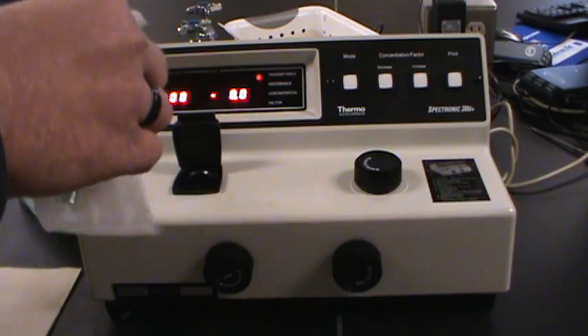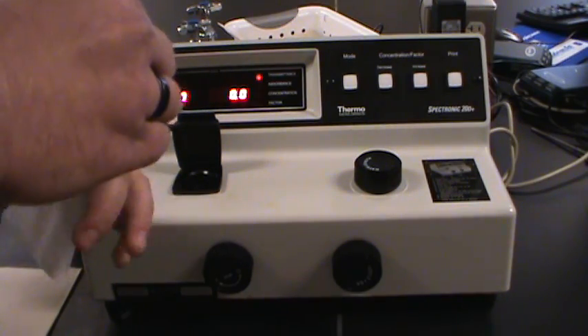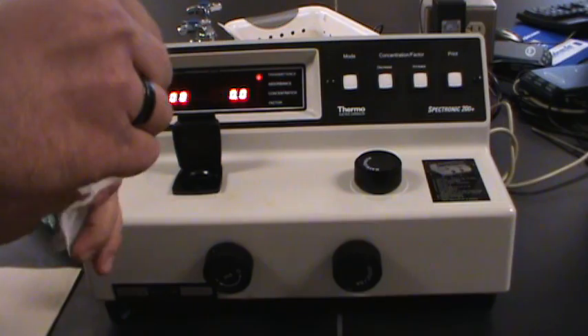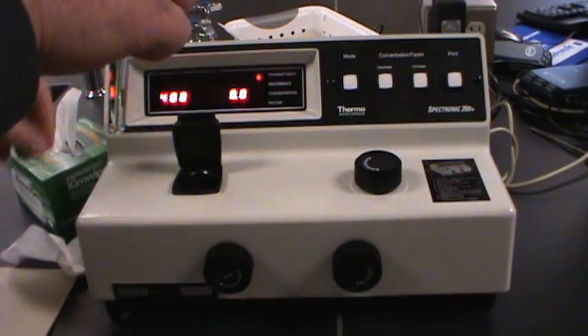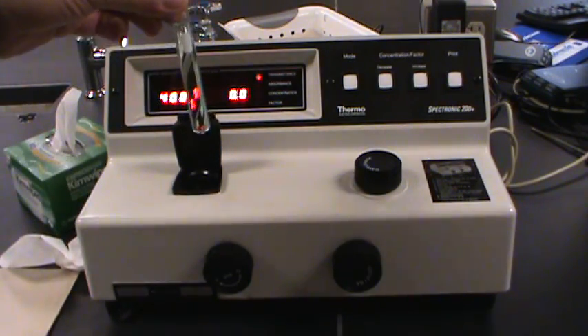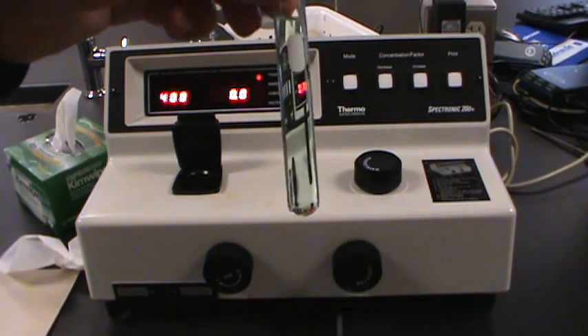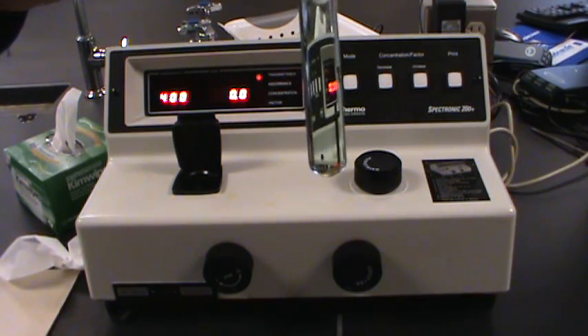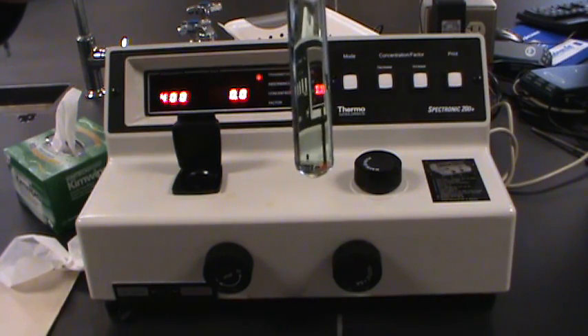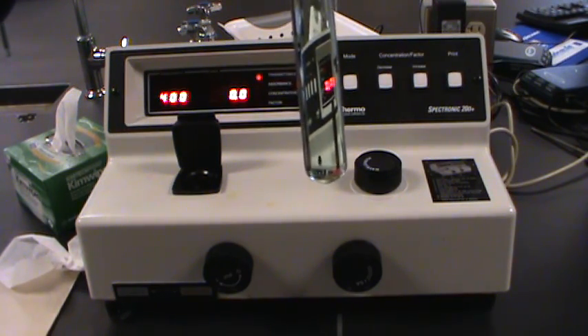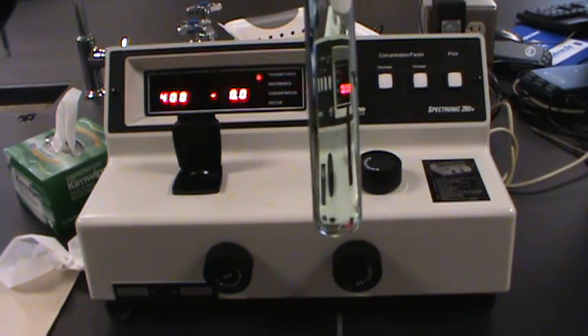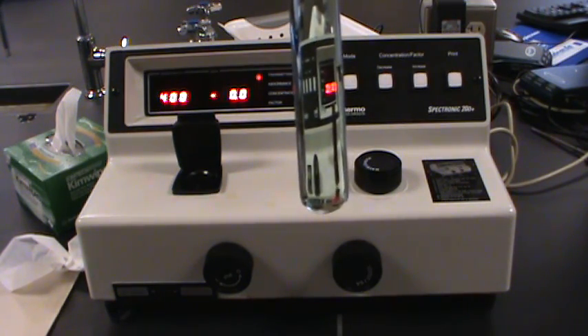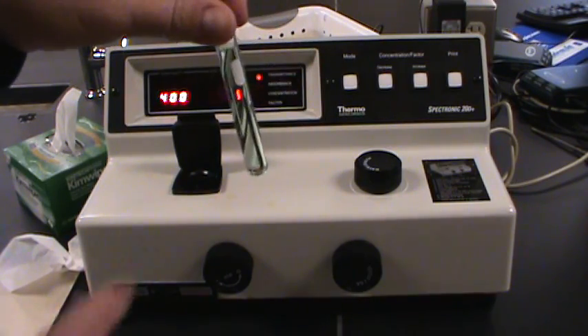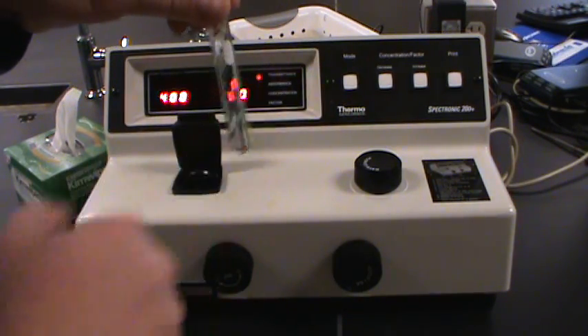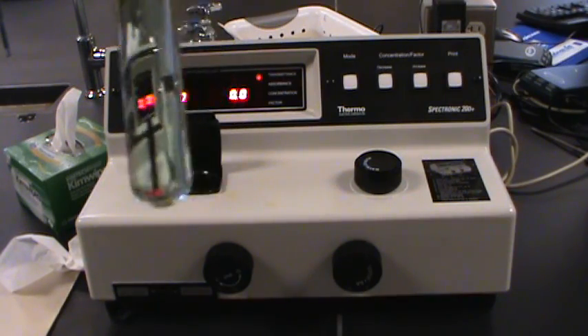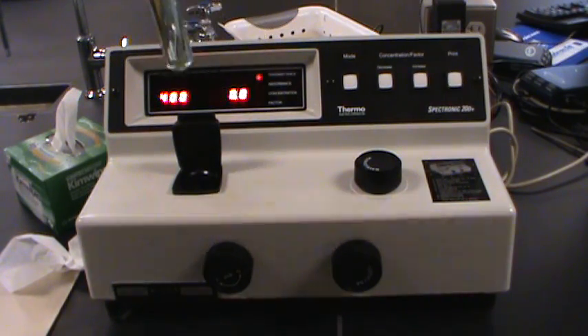So again, let's wipe the outside of that tube off. Make sure we don't have any fingerprints or smudges. And I just noticed something in this tube. Let's see if I can bring it close enough to show you. There it is. See the bubbles? There are two or three little bubbles in this tube, and those little bubbles could cause trouble if the light beam is passing through at the bubbles. So let's just give it a smack, and that loosened up the bubbles. The bubbles all came out.